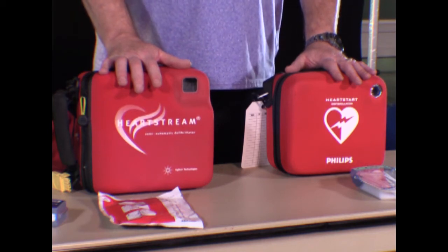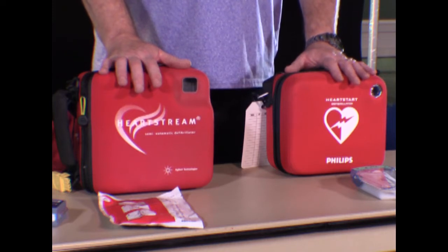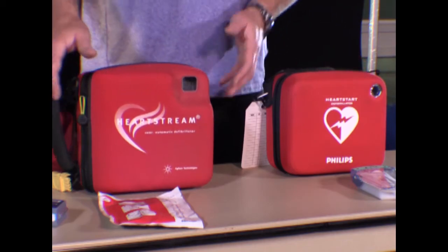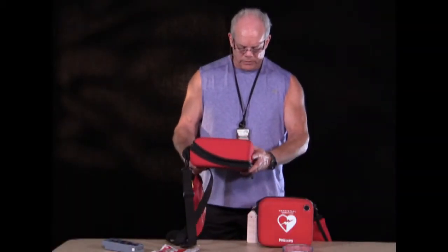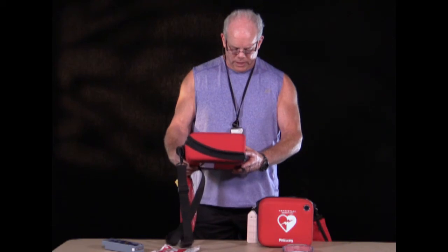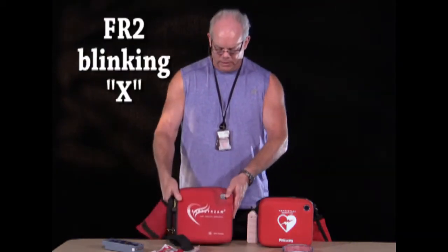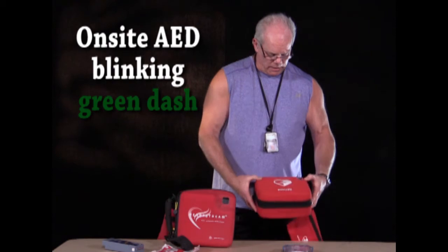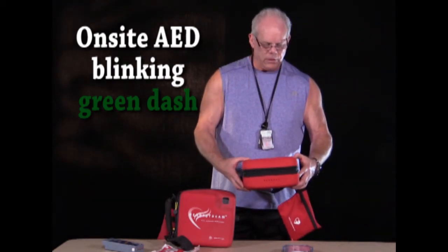So first we need to do a safety check. This will only take about 2 minutes, and then you'll need to initial the card that everything is working. The first thing we can do is look at this little screen on the top right of both these machines. There is a blinking X on the FR2, and on the on-site defibrillator it's a blinking green dash. That's the first thing you can check to make sure that everything is working in the battery. If the batteries are not working properly, there will be a chirp coming from the machine. Hopefully we'll never get to that point, hearing a chirping, before we replace the batteries and replace the pads.